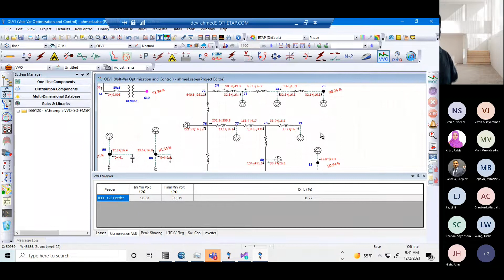But okay, so that is the Volt-VAR optimization. And in this Volt-VAR optimization, the good thing is we have all the phases - phase A, phase B, phase C, and combinations AB, BC, CA. So that's actually a very good unbalanced system to check our results. I know some groups are working with Volt-VAR optimization, so I think we can compare the results - what we are doing versus what already exists.